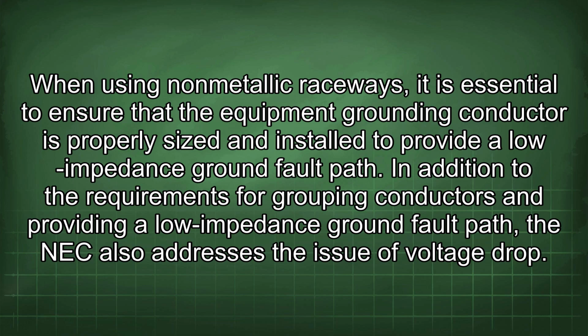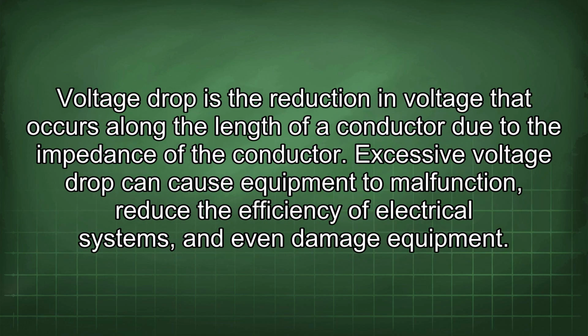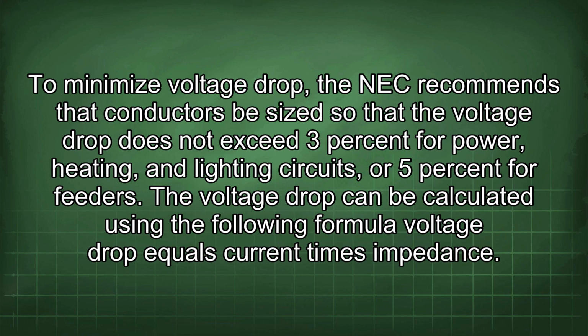In addition to the requirements for grouping conductors and providing a low impedance ground fault path, the NEC also addresses the issue of voltage drop. Voltage drop is the reduction in voltage that occurs along the length of a conductor due to the impedance of the conductor. Excessive voltage drop can cause equipment to malfunction, reduce the efficiency of electrical systems, and even damage equipment. To minimize voltage drop, the NEC recommends that conductors be sized so that the voltage drop does not exceed 3% for power, heating, and lighting circuits, or 5% for feeders.